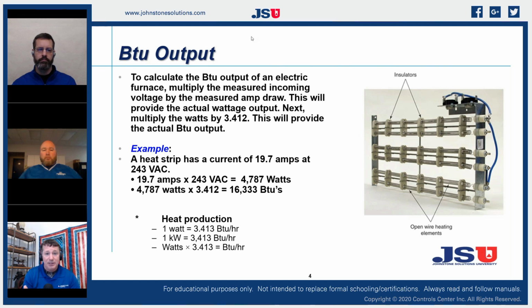and typically does it 100% efficient. So for each watt of electricity we're bringing in, we're producing a watt of heat out. But if we think about what that wire is, it's a material that's designed to run in a certain temperature range. And like all materials, particularly all metals, at some temperature, those things are going to break down, right? So we try to maintain a fairly specific temperature on our elements. And once we get above that temperature, we're going to start degrading the actual element itself, and we're also going to overheat those ceramic insulators.